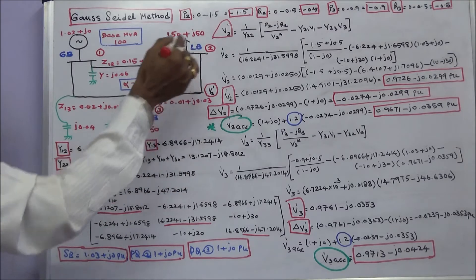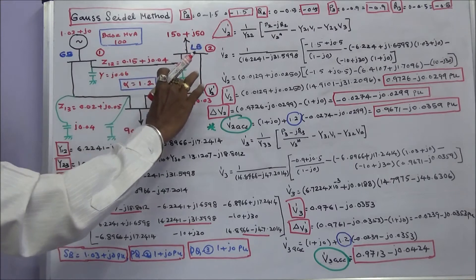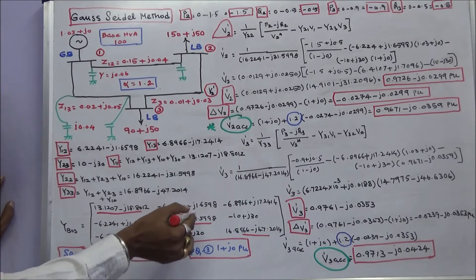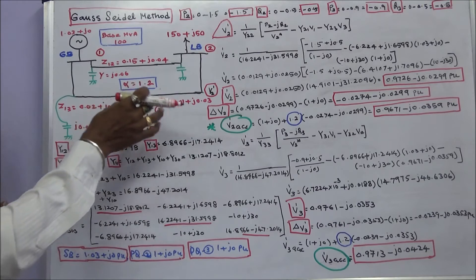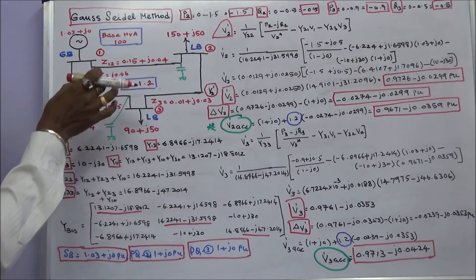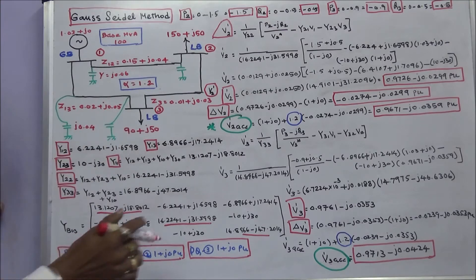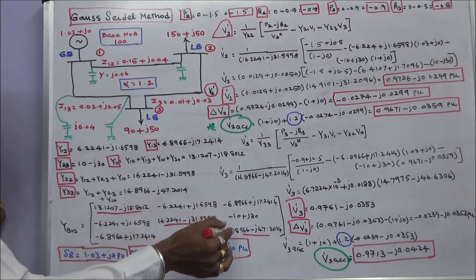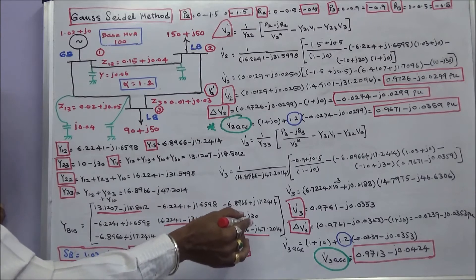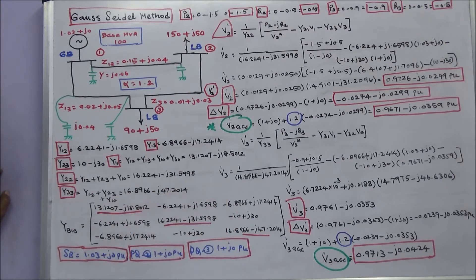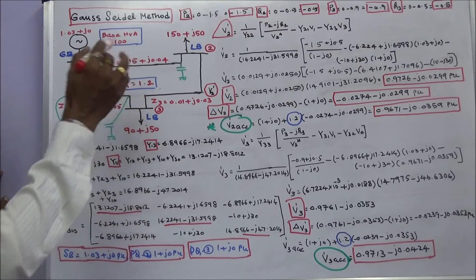Y22 is equal to its admittances plus half-line charging admittance. Y33 is equal to its admittances plus half-line charging admittance, giving Y33 equal to 16.8966 minus j47.2014. These are the diagonal elements. We also have to calculate the off-diagonal elements, completing the Y-bus matrix of the system.